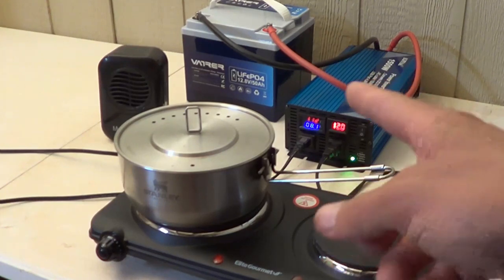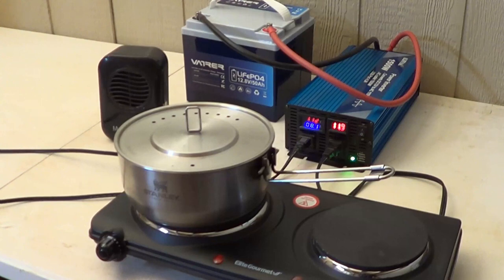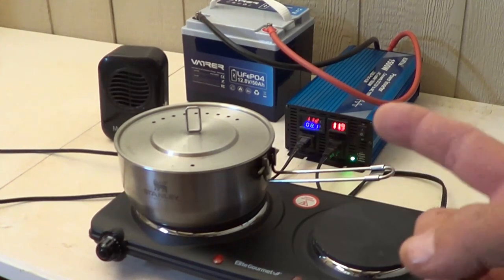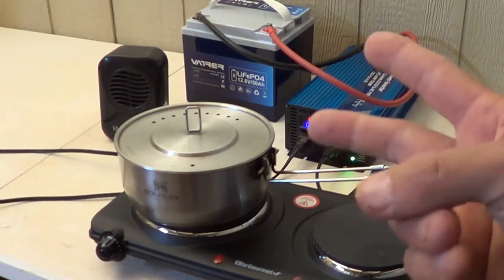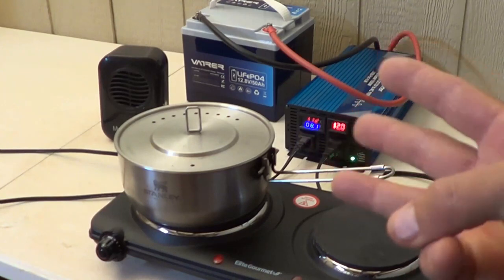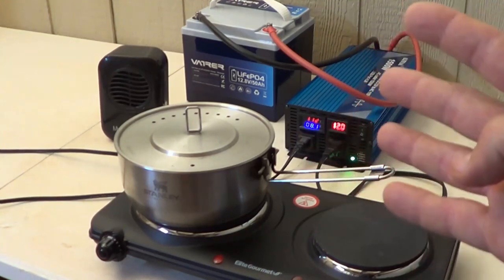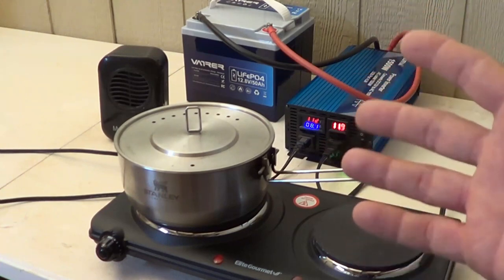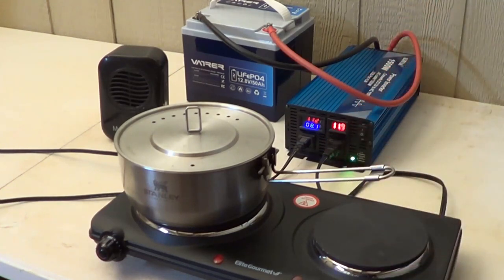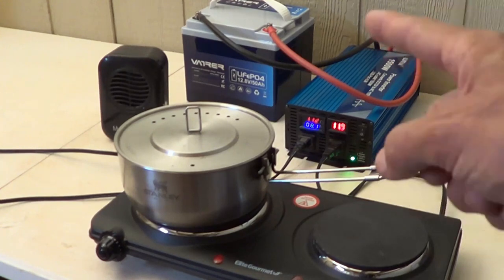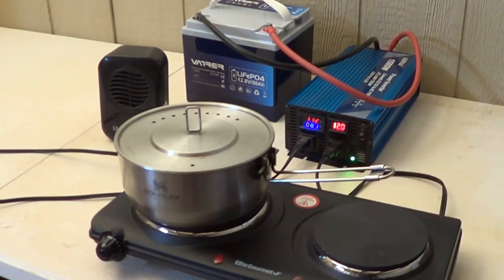The 50 amp BMS on this battery has lots of protection systems. It has overcharge protection, over discharge protection, over current protection, over voltage protection, over load protection, short circuit protection, and high temperature cutoff protection. That prevents the battery from charging when the temperature gets above 167 degrees Fahrenheit, which is 75 degrees centigrade.